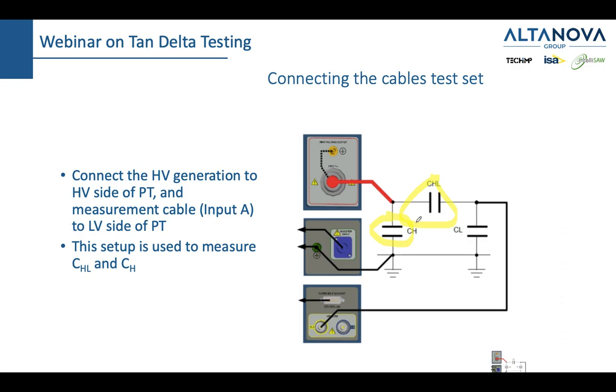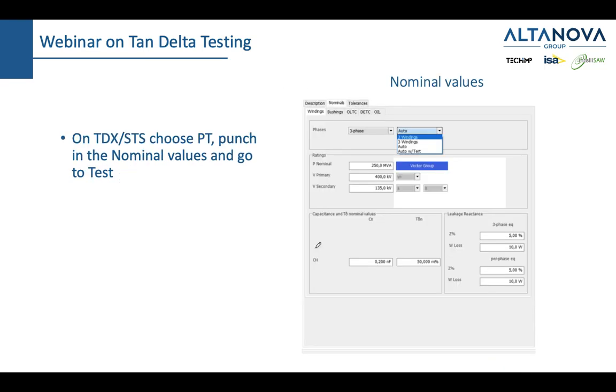Now, as you have connected and grounded properly your system, you need to punch in the nominal values. It's necessary to say whether you have a three-phase or single-phase transformer, and whether you have a two or three winding transformer or auto transformer with tertiary. That depends on what type of transformer you test. But it's also a good idea to write the nominal values of your tan delta and capacitance, because then you can get an automatic assessment of whether your result is good or bad, so pass or fail.